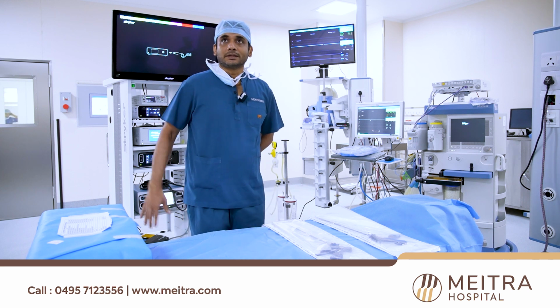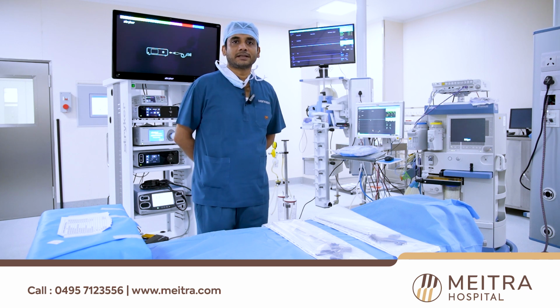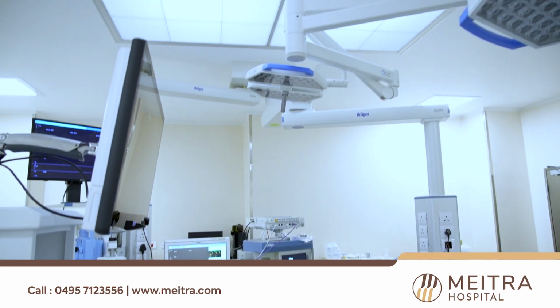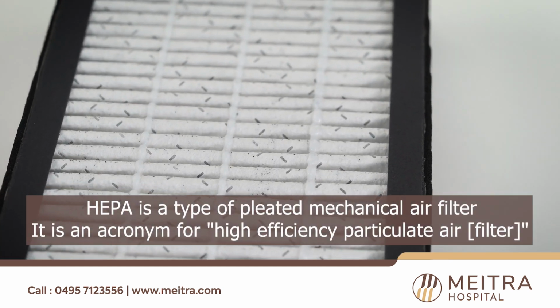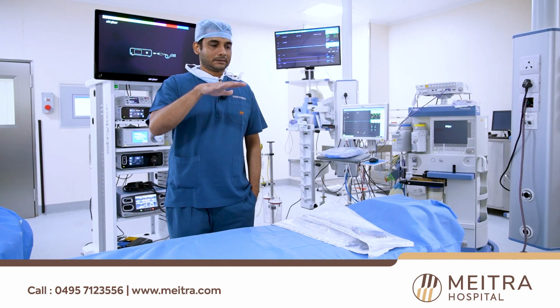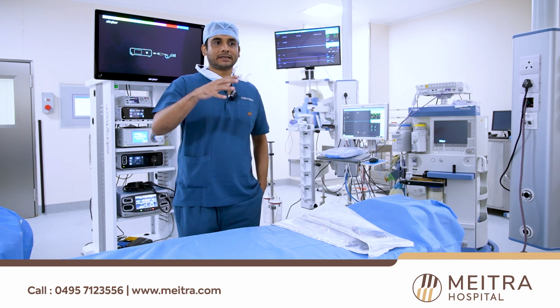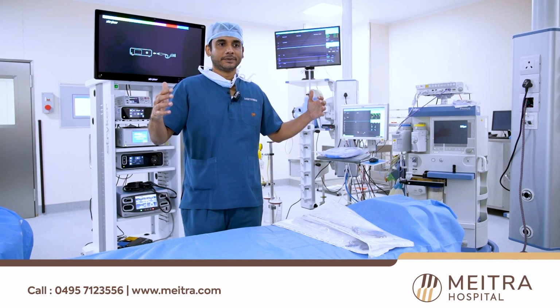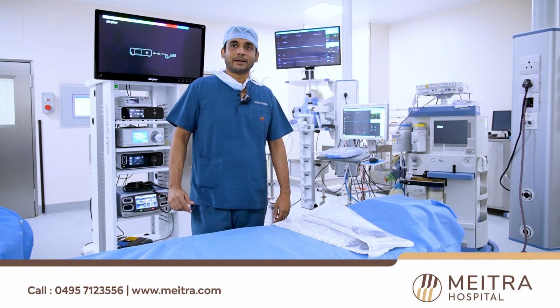I'll start with the operation theatre itself. In the operation theatre, we have something called laminar flow. Most of the air comes from the HEPA filters. These are the HEPA filters you see above. It's a filter which prevents any microorganisms from coming into the operation theatre. The pressure inside the theatre is maintained at about 2 to 3 pascals, so the room has high pressure. This prevents air from coming into the room, so the only air which comes in is through the laminar flow.